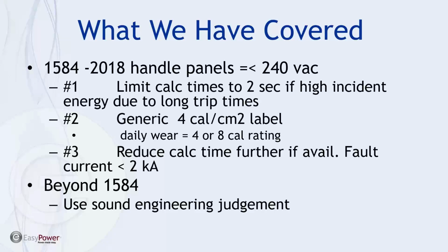And for what it's worth, EasyPower has the ability to do both. In DC, we use the max power method, which is, again, generally accepted to be the way to do DC arc flash. And for single phase, we calculate the single phase current and then use the 1584 model to calculate incident energy. Both of those methods are considered to be conservative, so use those options in the tools accordingly. So that covered what I wanted to discuss. There were a couple of questions.